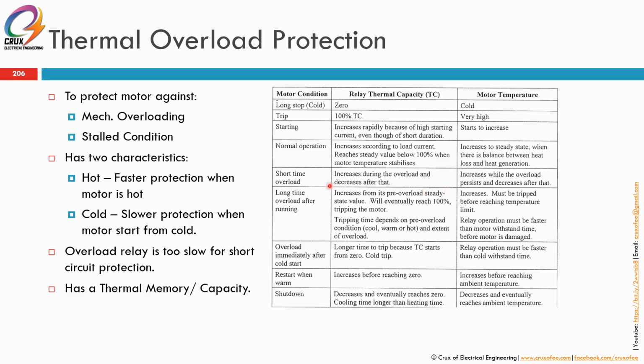Thermal overload protection is to protect the motor against mechanical overloading as well as stall condition. This stall condition can happen during starting or during the course of running of the motor. It has two characteristics: one is the hot curve, another is the cold curve. The hot curve is faster protection when the motor is hot, meaning it trips faster compared to the cold curve. Whereas the overload relay is too slow for short circuit protection, so an overload relay is not used for short circuit protection. That's what it's trying to convey.